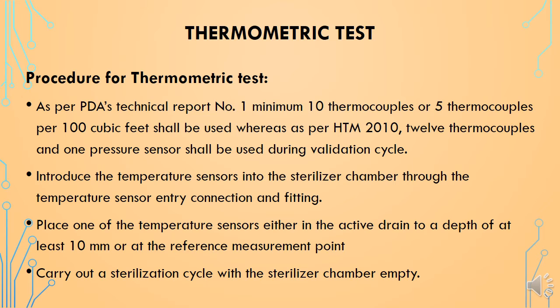Introduce the temperature sensors into the sterilizer chamber through the temperature sensor entry connection and fitting. Place one of the temperature sensors either in the active drain to a depth of at least 10 mm, or at a reference measurement point. Carry out the sterilization cycle with the sterilizer chamber empty.